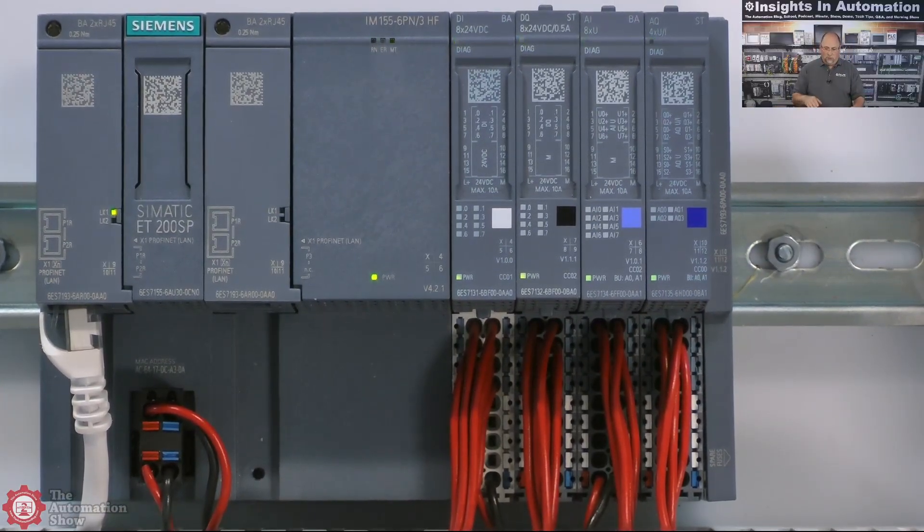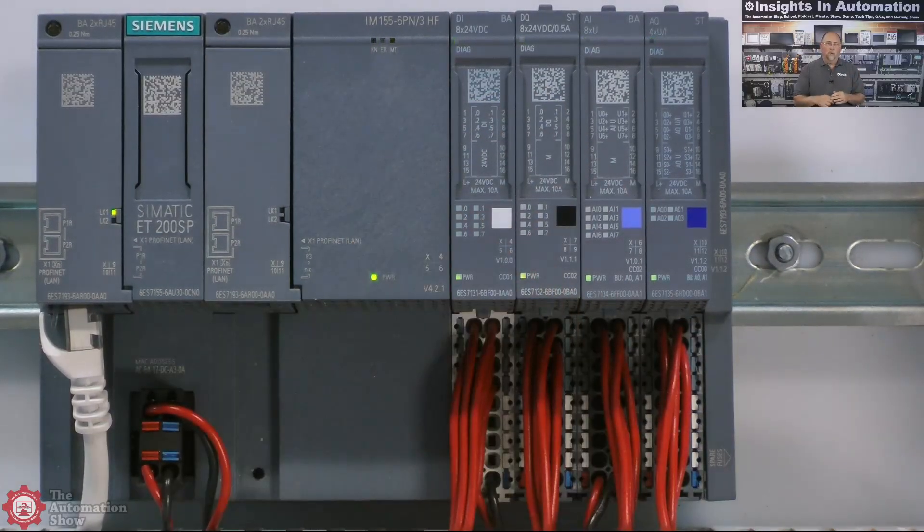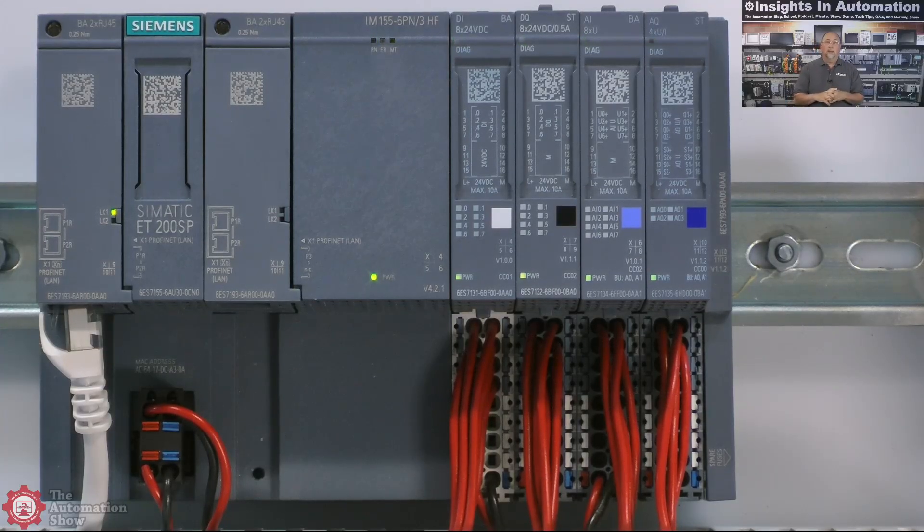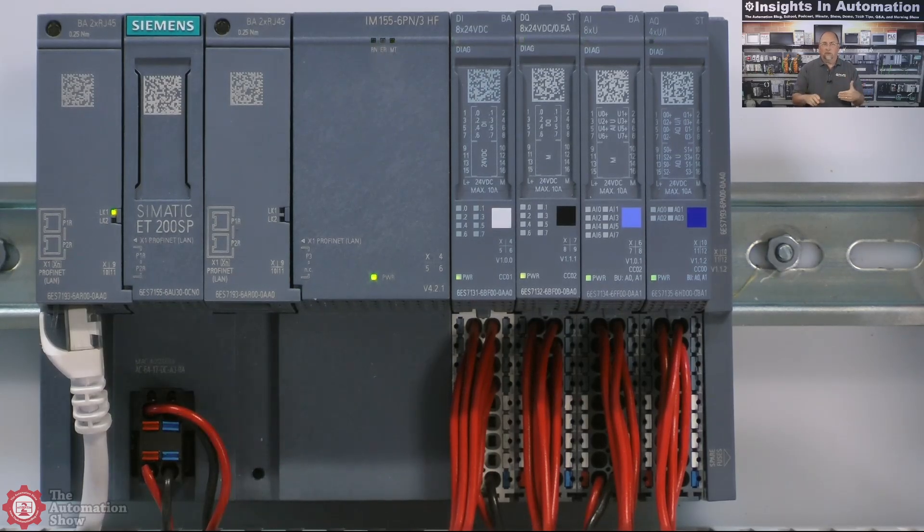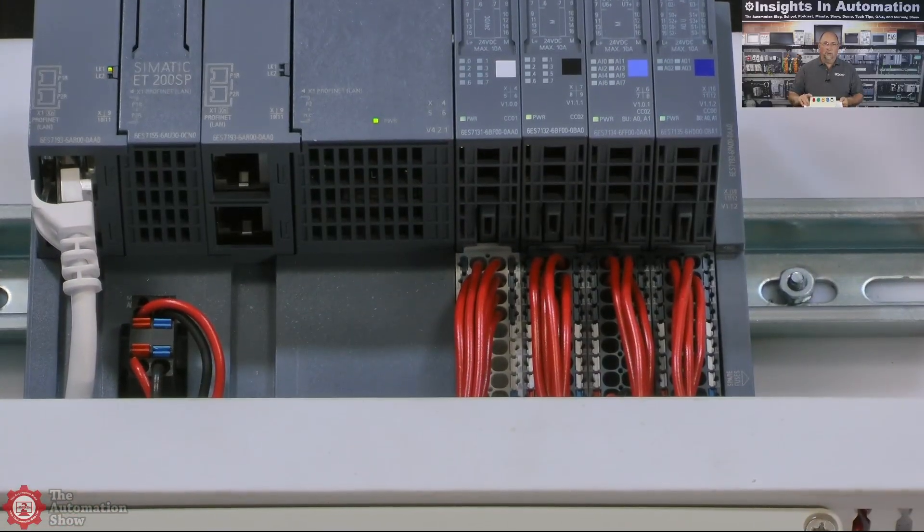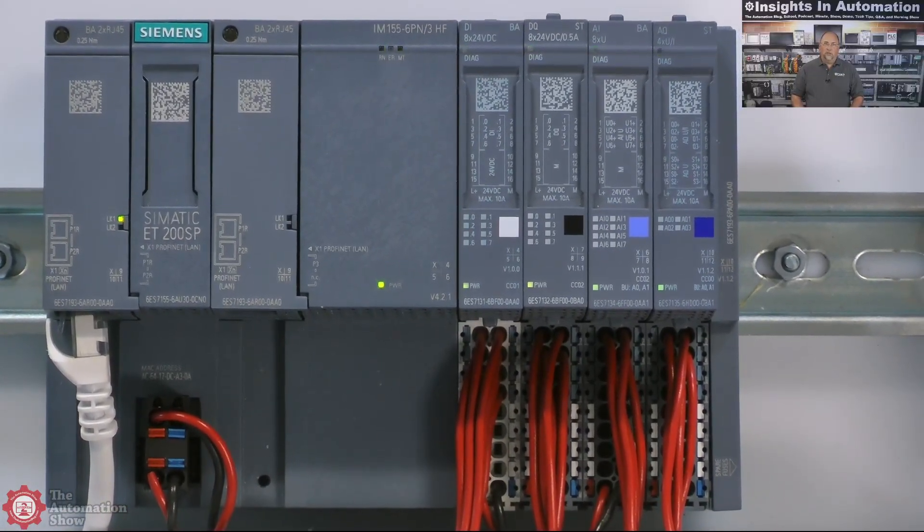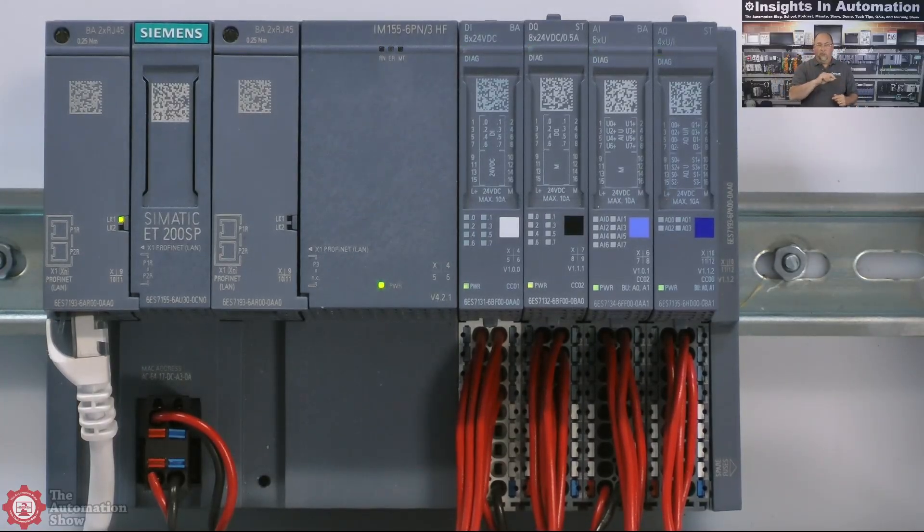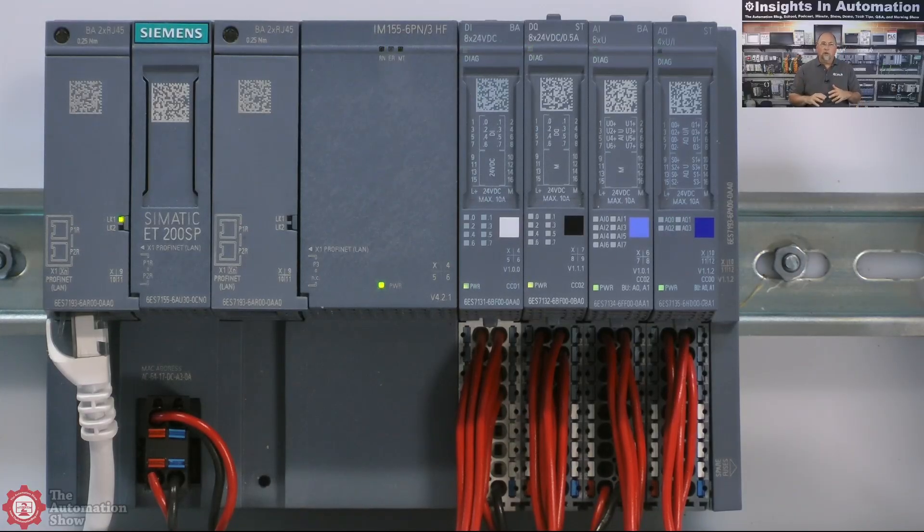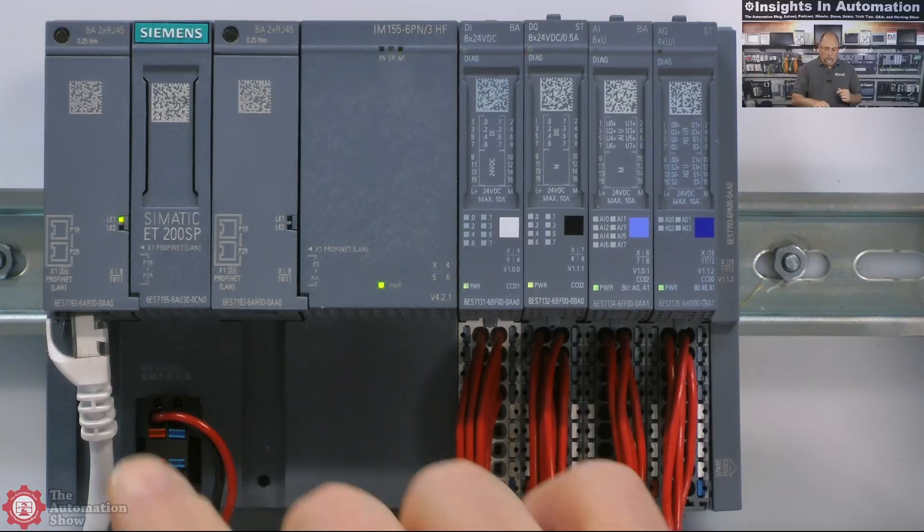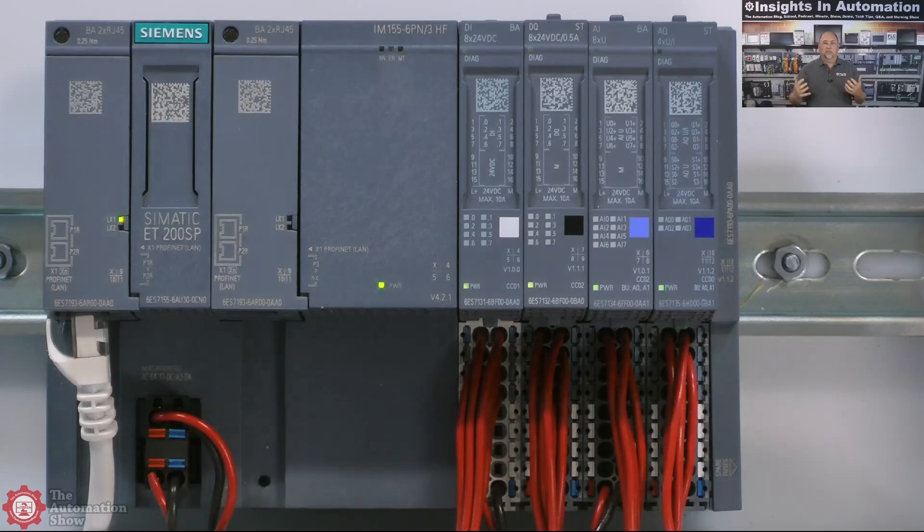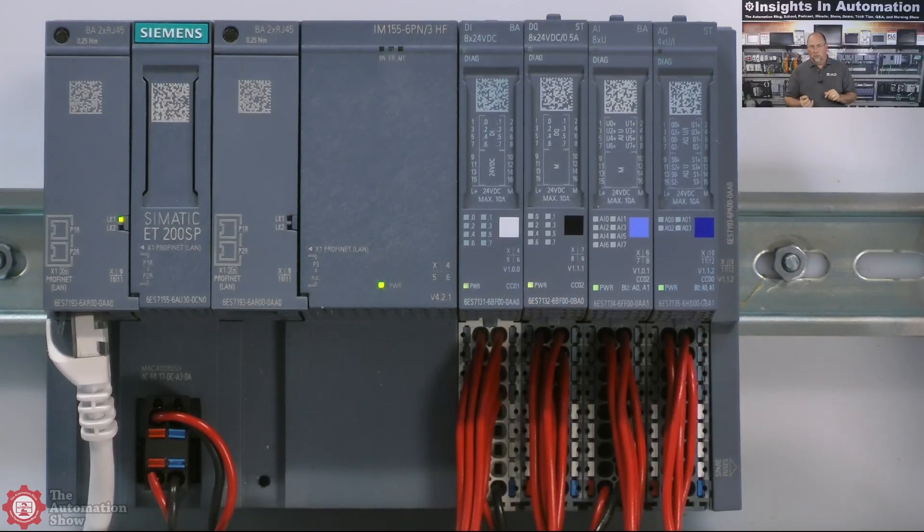I'm really zoomed in on it. This is the interface module, the IM 155-6PN 3HF. Unlike the one we looked at in the previous episode, this one is not a standard, it's a high functionality. And it actually lets you have up to three ports on it. You can see it actually has four ports, but you only can use three of them. This is great for those situations where maybe you're daisy chaining from rack to rack to rack out there in the field from distributed IO to distributed IO. But you need a port for maybe a bulkhead connector so you can program or you have an HMI in that cabinet.